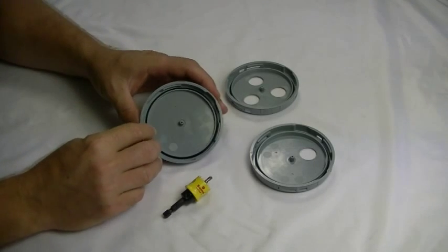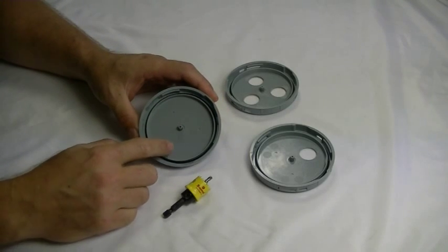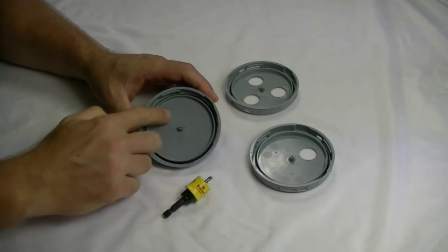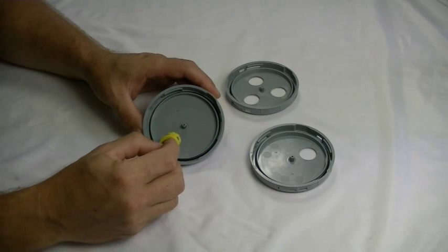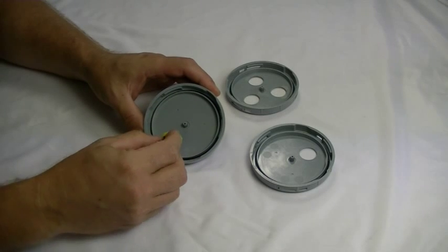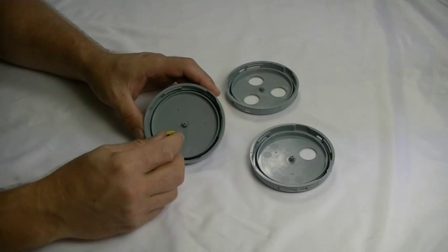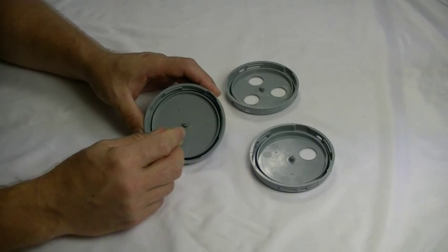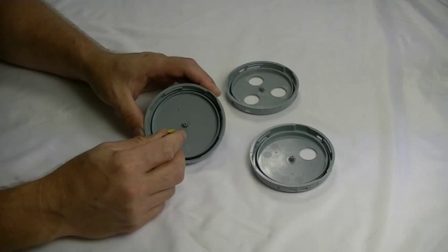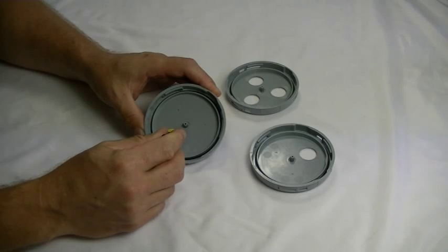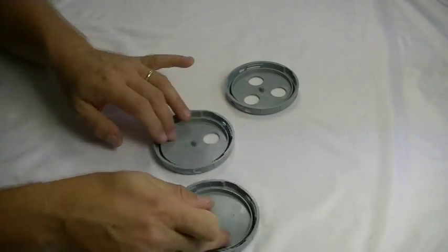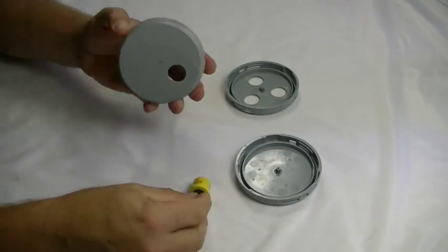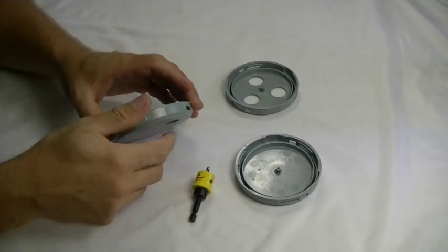On the lid, the gland locations are marked by three small depressions. Simply locate the pilot drill of the hole cutter into the depression to ensure that the cut will be in the correct position. Once the holes have been cut, the glands can be fitted.